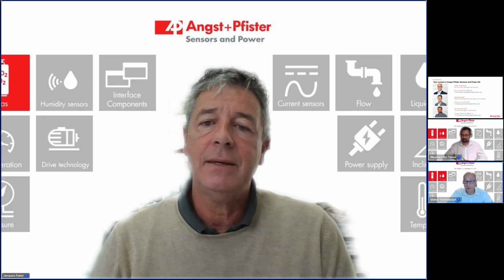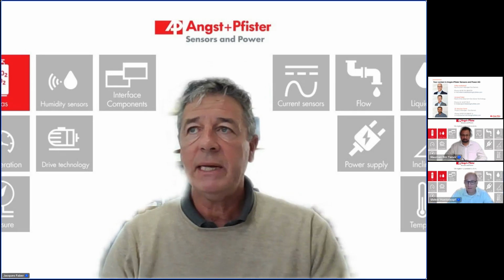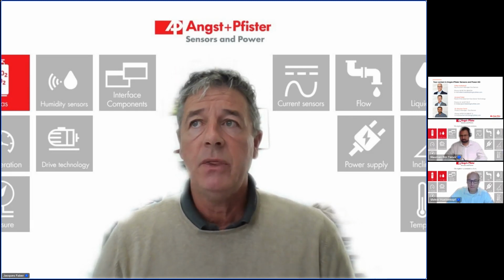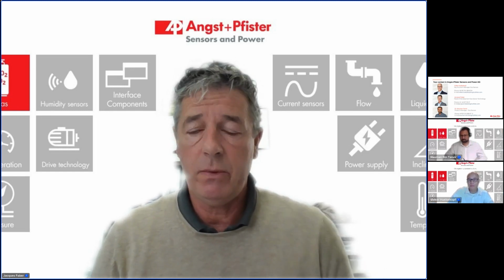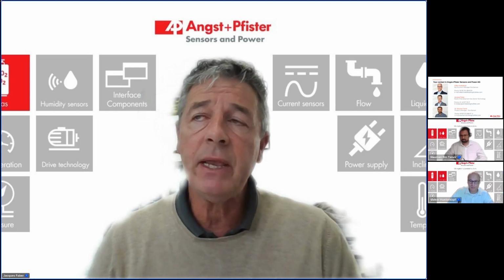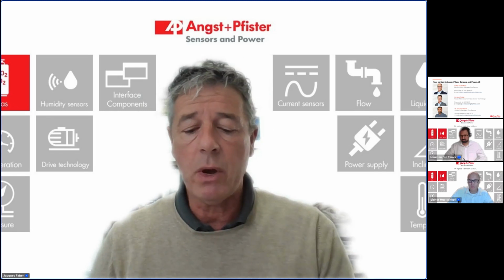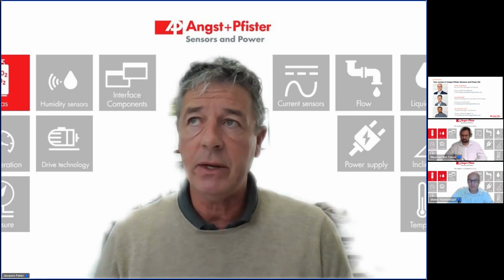We have a lot of real practical questions here, like this one. What are typical gas flow rates? If you just use an oxygen sensor without any bypass, then you should go to 100 milliliters per minute, which corresponds to 6 liters per hour. But in order to make sure that you don't destroy anything, it would be useful to use a bypass or a so-called flow regulator. The flow regulator is a mechanical part, so no electronics are required. It is always built into our analyzers. With the flow regulator, you can apply from, let's say, 20 to 90 liters per hour, and it makes sure that the flow through the measuring cell is always at 6 liters per hour.